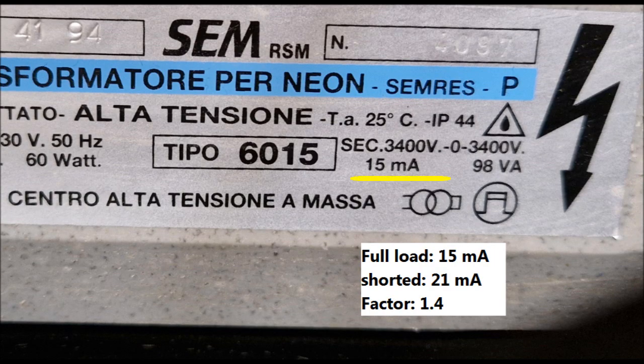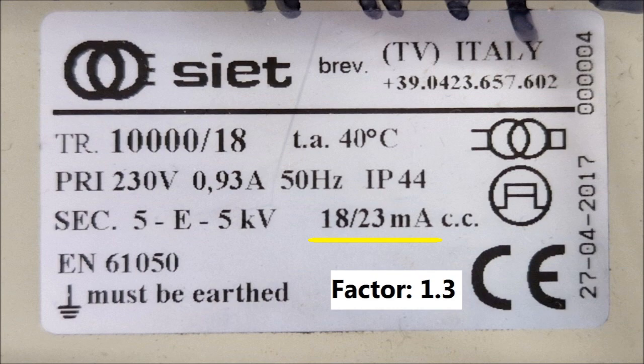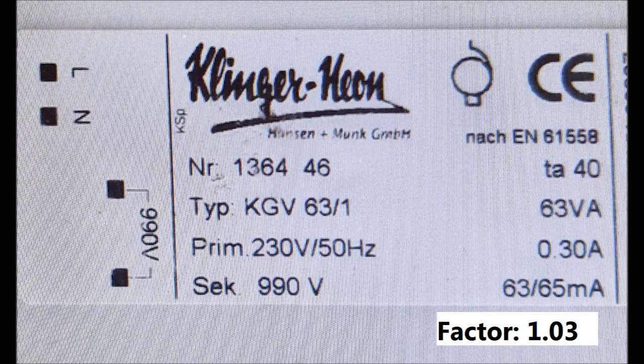In Europe it's different. When you only have one value on the nameplate, it's the nominal current — that means at full tubing length. If we have a shorter tube or a short circuit, the current will be higher than what's on the plate. If you are lucky, the Euro transformer has both values on the nameplate, so you have all the information at once. The factor between nominal and max current can differ depending on the transformer's internal construction.